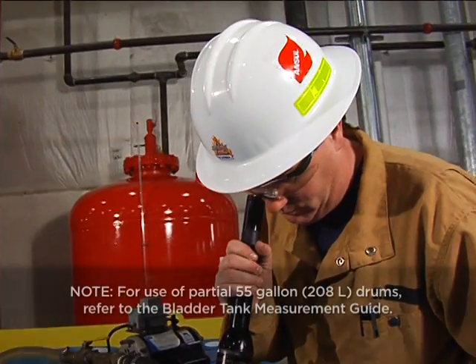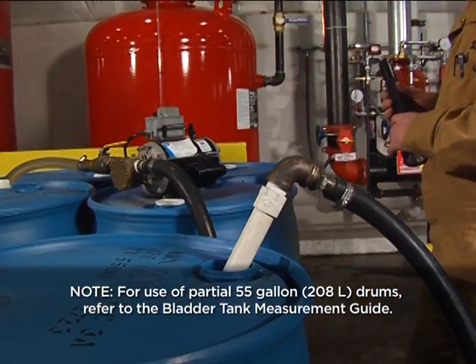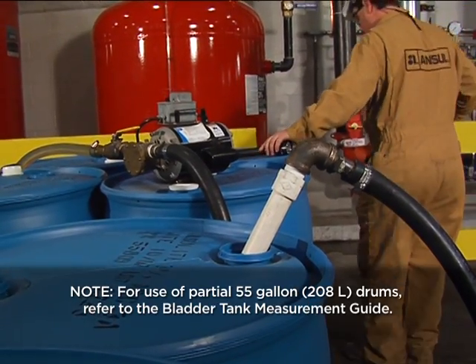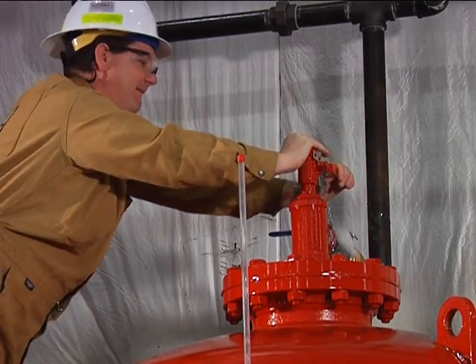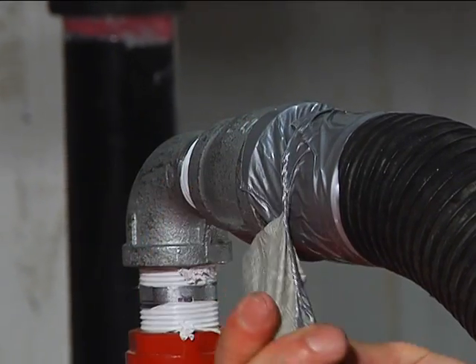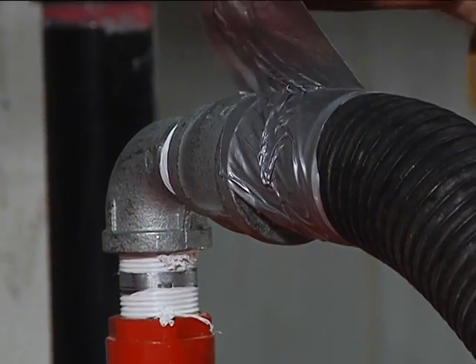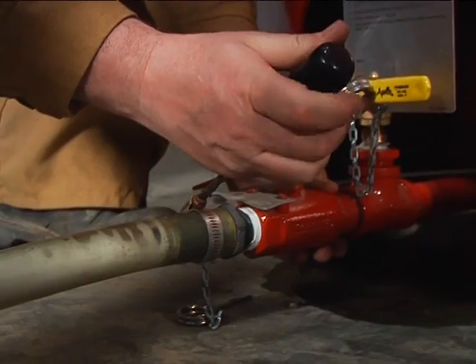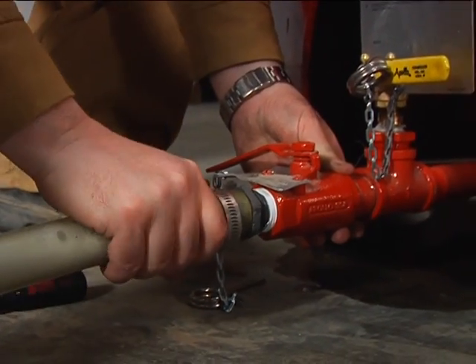Once the bladder tank is filled to the rated capacity stamped on the tank nameplate, close the bladder drain fill valve, shut off the concentrate fill pump, and close the bladder vent fill valve. Disconnect the vacuum hose from the tank shell vent valve. Disconnect the concentrate fill pump from the bladder drain fill valve.